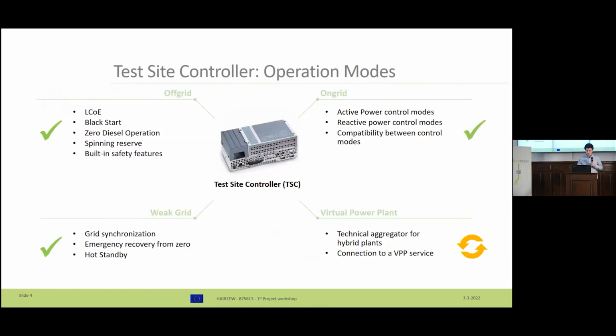This is our controller, which controls all the assets and devices in the facility and has 4 different modes depending on grid quality: off-grid, on-grid, weak grid, and virtual power plant modes. Off-grid is when there's no grid available, so you need to create one using the gensets or batteries. In this case, grid stability is the most important parameter; once stability is achieved, you can control other parameters like levelized cost of energy.